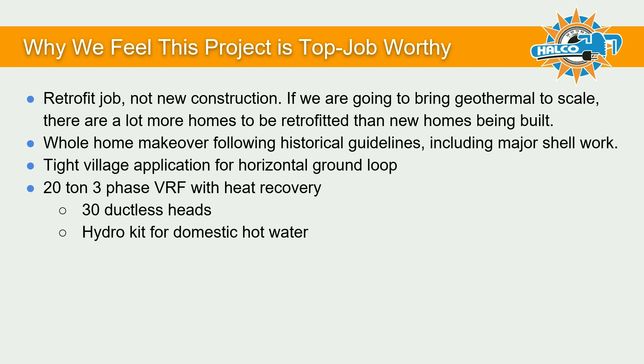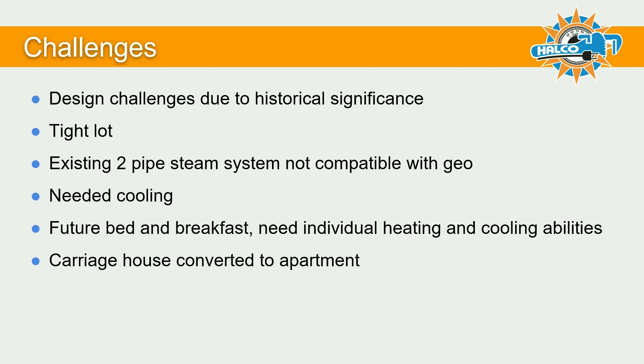Like I said, challenges. It's a tight lot. Trying to build something like this, a mini split style system, in a house that only has radiators, doesn't have any ductwork. We weren't going to go tearing walls out to run ductwork all over the place. So what we did is we went with the mini splits, to try to keep it within the historical aspect of the house as much as possible. Like I said, existing two-pipe steam boiler, not really great for Geo with cooling.